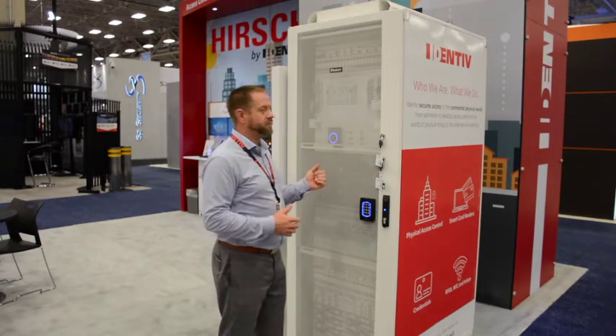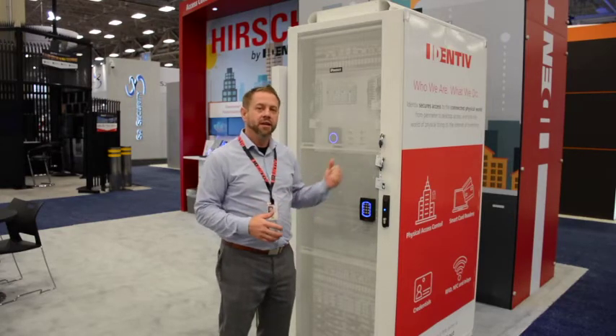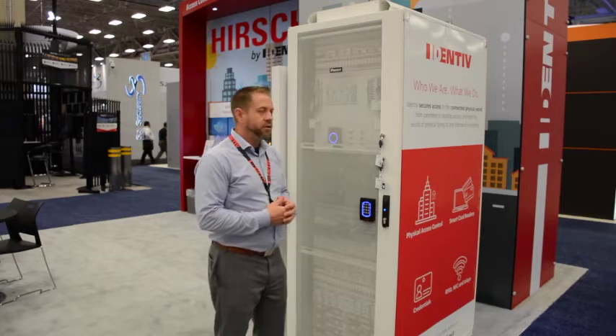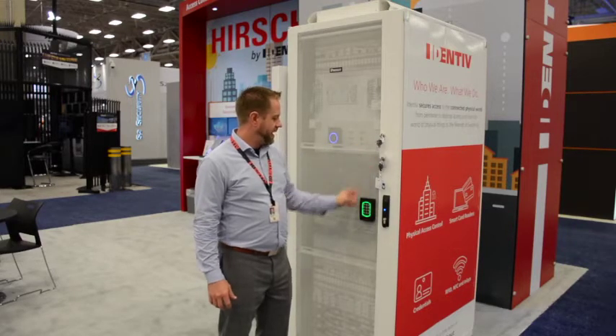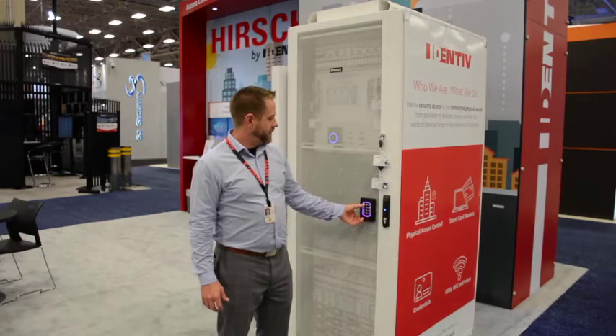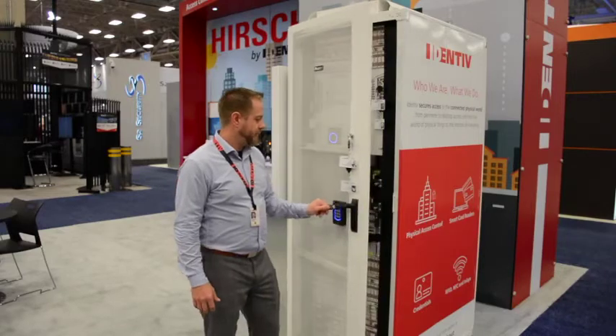That can be independent front and back door control covering 12 racks, or 24 racks with serialized front and back door capability. We do this by using the door code with a keypad reader — present a badge and enter your PIN, which for this demo is just zero, then star, the door number, and then the pound key. That's going to open door one for our rack.